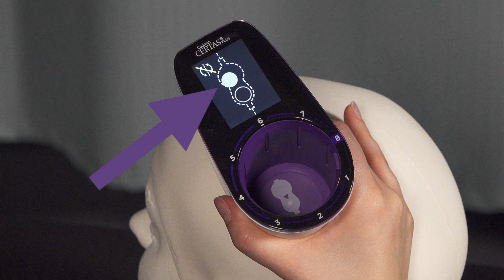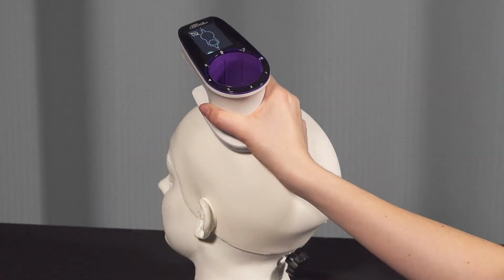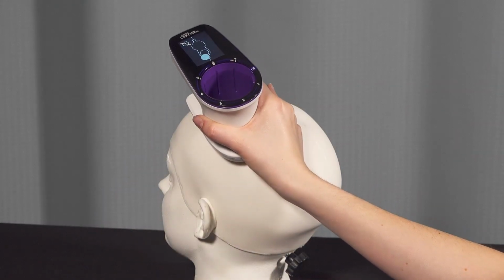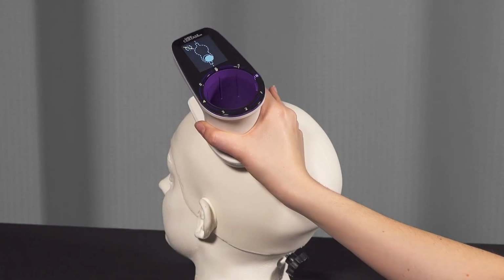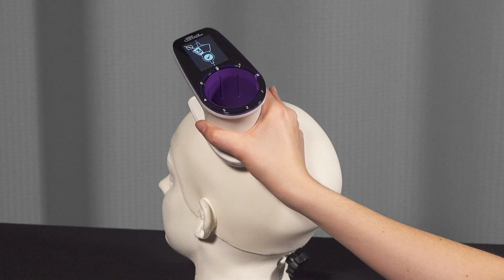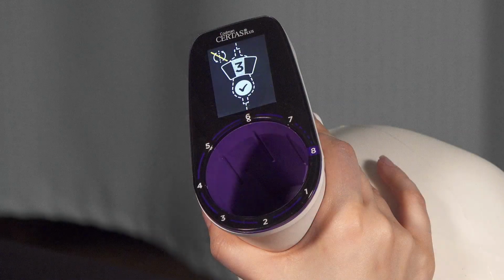With the concave section of the locator base in contact with the patient, move the locator in a linear direction to align the locating dot with the circle in the valve silhouette. Maintain the proper orientation of the direction of flow. Once the locating dot is centered, the locating dot will illuminate white with a check mark, and indication windows will appear. A single, fully visible number within the window indicates the performance setting of the valve.